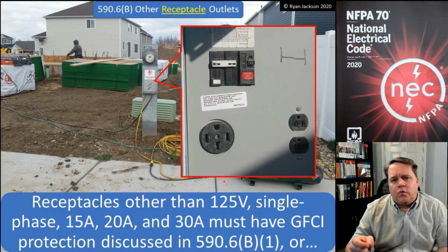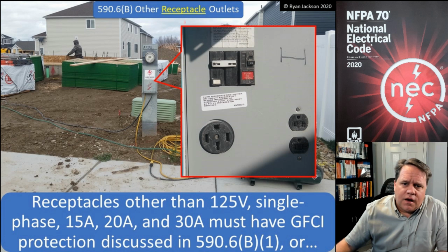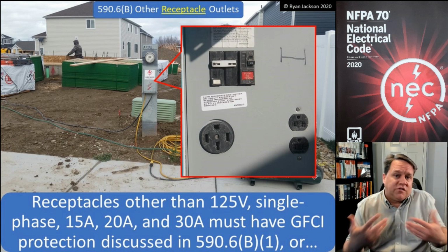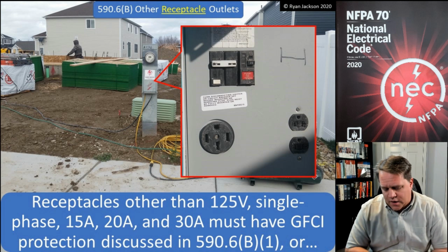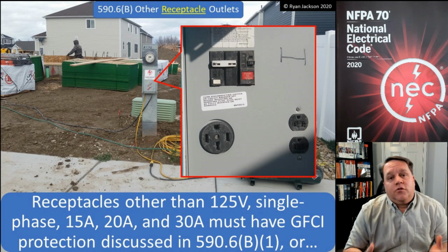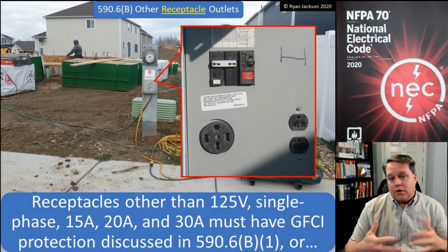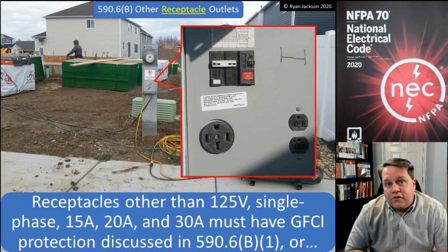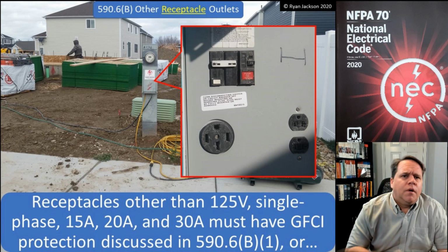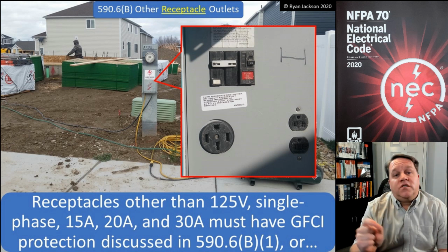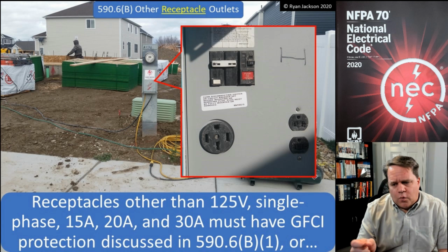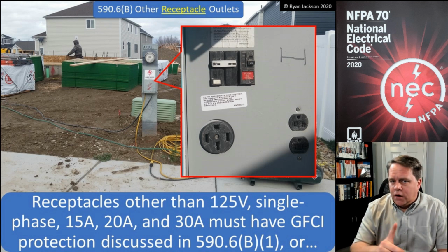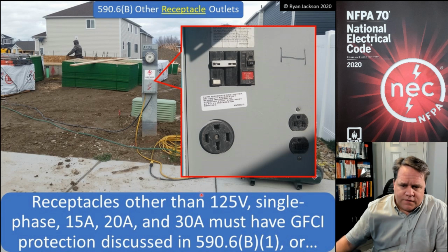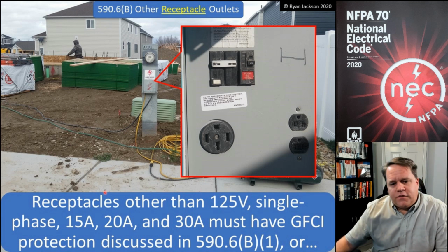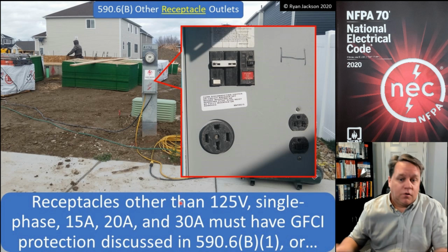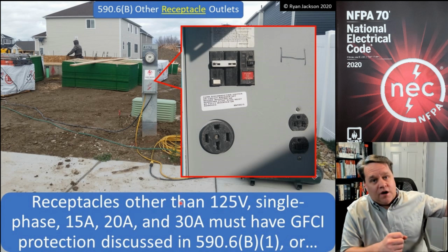590.6(B) talks about other receptacle outlets, and you can see the highlighted underlined text there, the word receptacle. It used to say other outlets. Okay, well, an outlet is not limited to receptacle outlets. Lighting outlets and hardwired equipment ultimately are connected to an outlet by definition, but we're talking about other receptacle outlets. Okay, well, other than what? Well, other than 125 volt, single phase, 15, 20, or 30 amp. Okay, so those ones, you have to have GFCI protection, period.